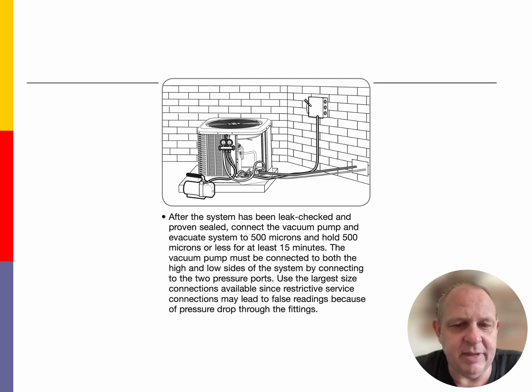After we pull it down into a certain micron level, and you're going to have to check the manufacturers on this, this Rheem manufacturer says 500 microns. I've run into Trane manufacturers that talked about 250 microns, and I've read up on Mitsubishi's that talk about bringing that system down to 1,000 microns, breaking that vacuum with nitrogen, bringing it down to 500 microns, breaking it with nitrogen, and then bringing it down deeply into the micron level that we want. And this is going to ensure that all the air and all the moisture is out of these systems.